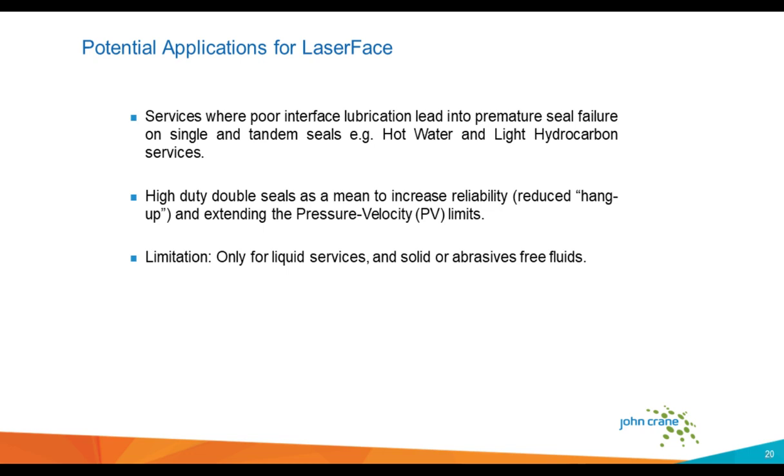So a potential application for LaserFace is a service where poor interface lubrication leads to premature seal failure on a single and a tandem mechanical seal. The seal is normally used in hot water and light hydrocarbon services, and in high-duty double seals, also as a means to increase reliability, reduce hang-up, and extend the pressure velocity, or PV, limits, as we call it.